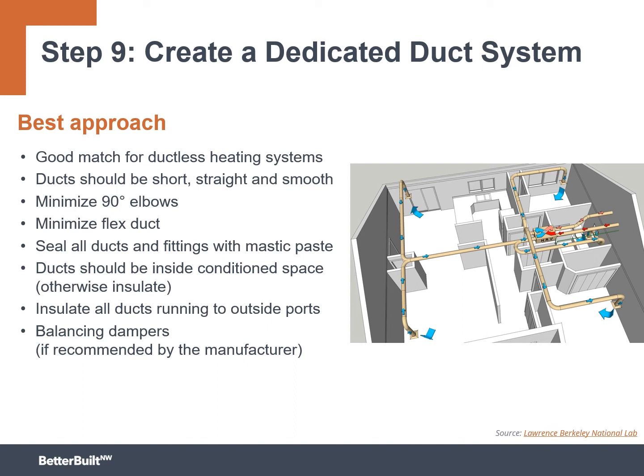Ducts are ideal if they're short, straight, and smooth. We don't want a bunch of 90-degree elbows. If you use flex duct, try to limit how much you use or make sure that it's been pulled tight and straight. You want to make sure that you seal all the ducts and the fittings with mastic paste, not just duct tape. Duct tape is great for just about everything in the universe except ductwork. Again, ducts should be inside the conditioned space or very, very well insulated.